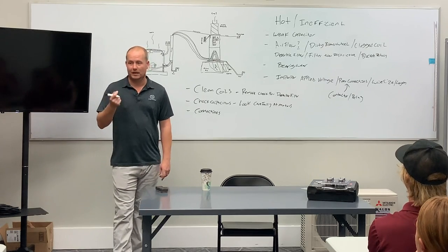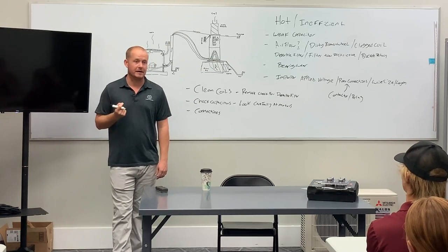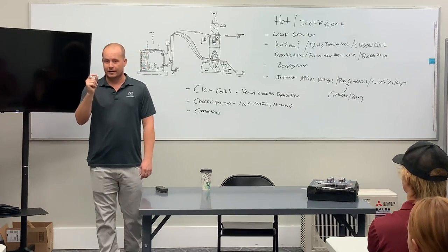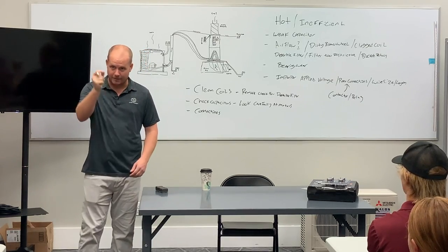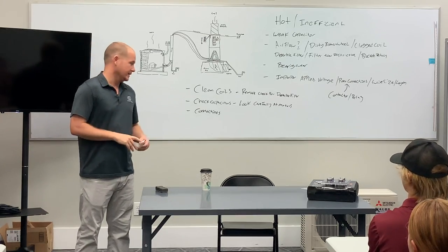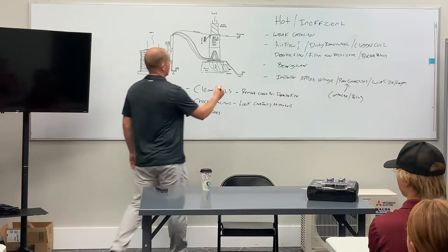Don't ever leave play in connections. Spade connections need to be hard to get on and off. If they go on easy, you need to take some needle nose and pinch them down so they go on snug.